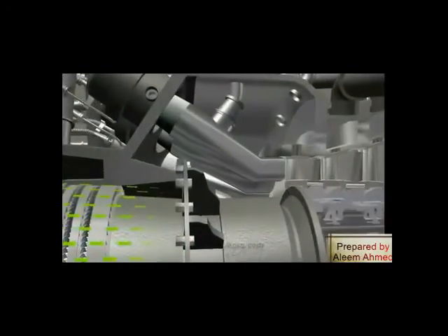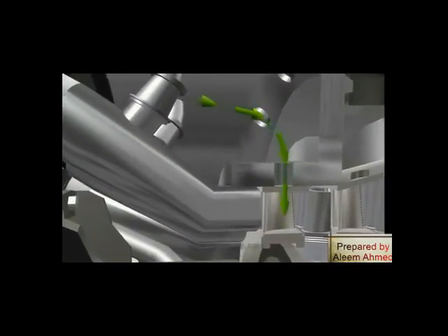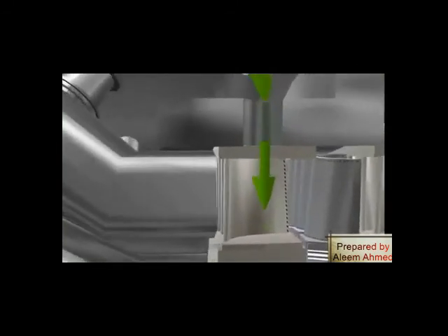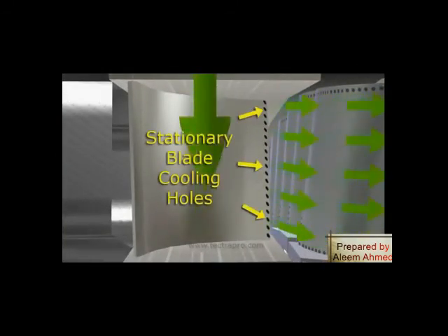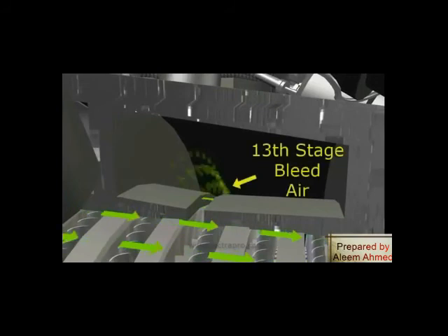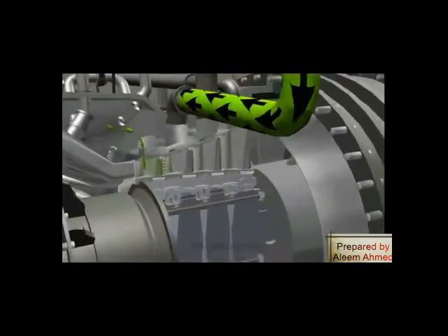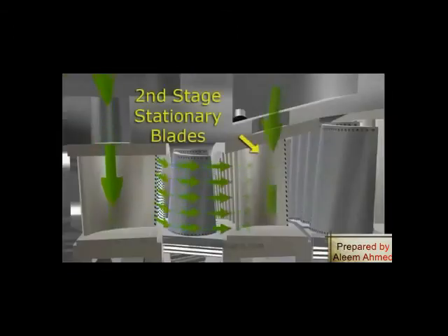Compressor discharge plenum provides cooling for the first stage nozzle. Once the machine is synchronized, the compressor bleed valves, or CBVs, close, and the air is redirected for cooling of the third and second stage nozzles of the turbine respectively.